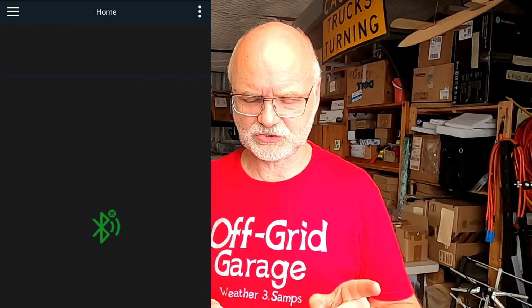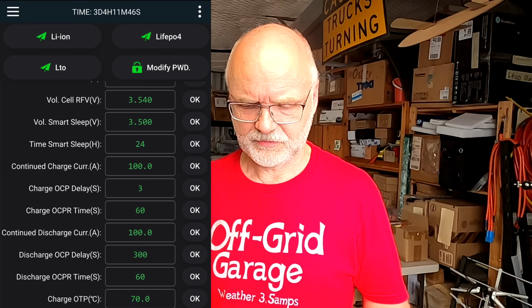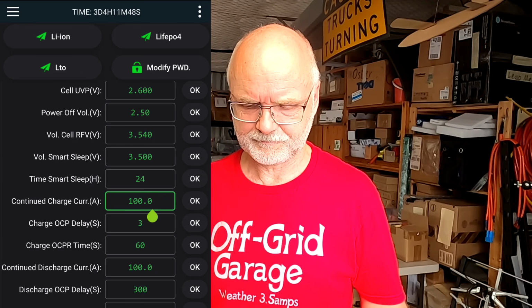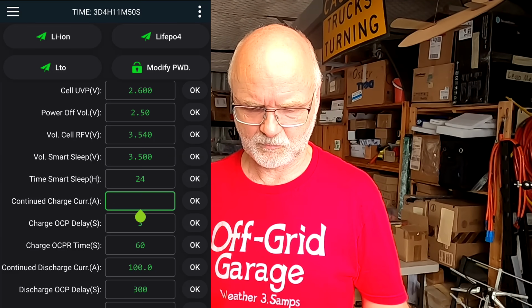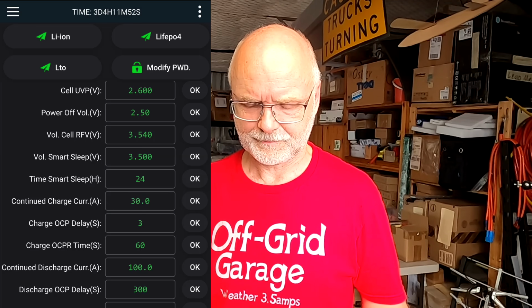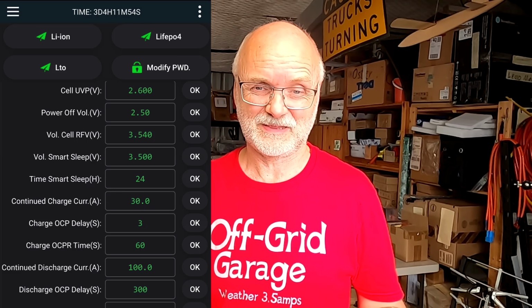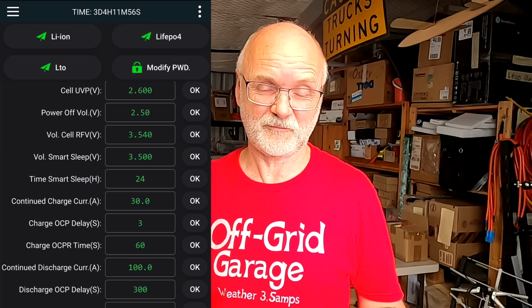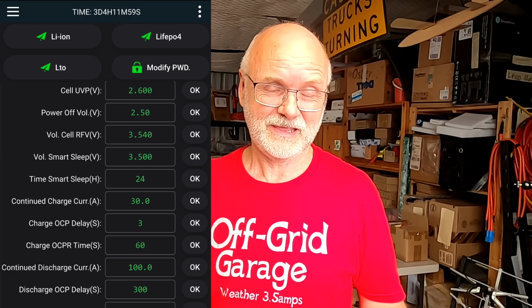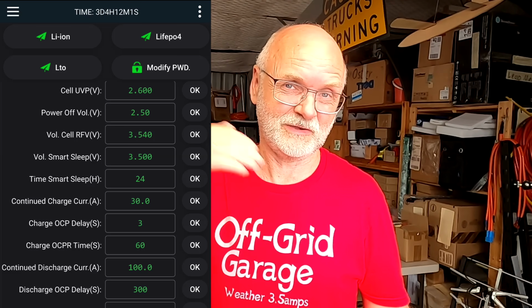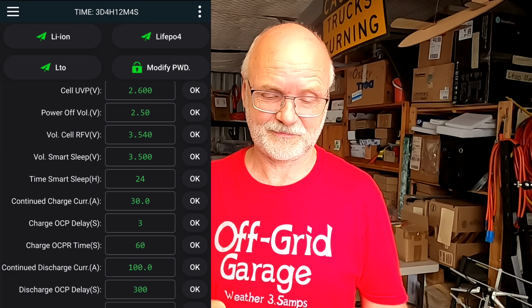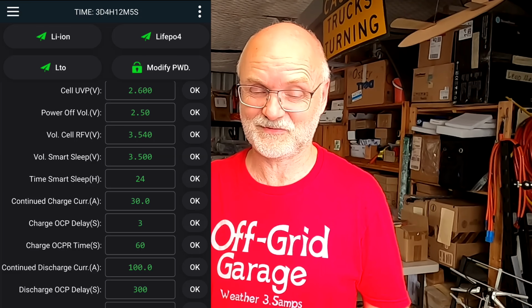What we can do is go into this slave battery and set the continuous charge limit to like 30 amps. So if we hit these 30 amps, the BMS usually would turn off, but now with the current limiter, it will just limit the current going into the BMS to 10 amps. So let's see if we can see 10 amps now.